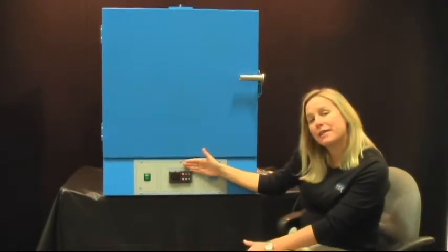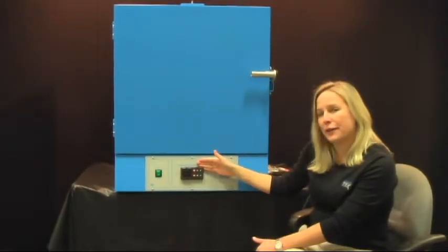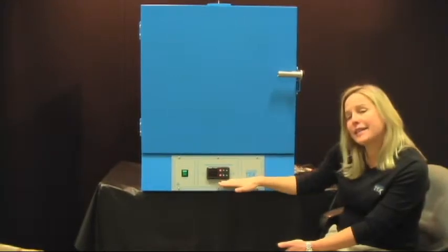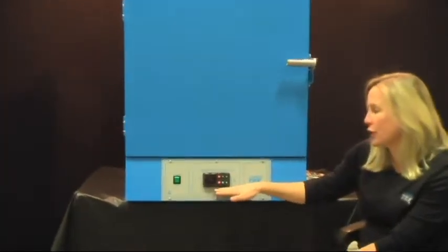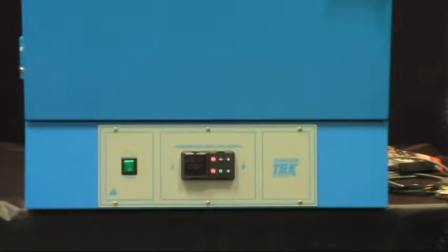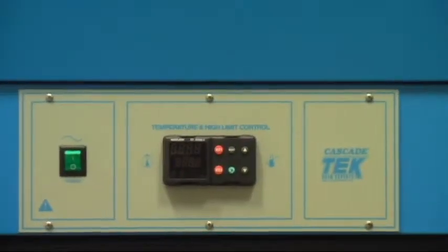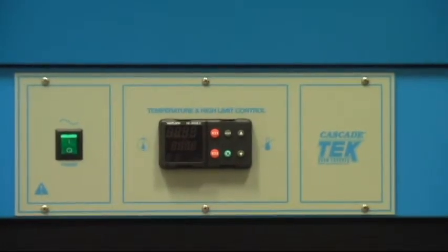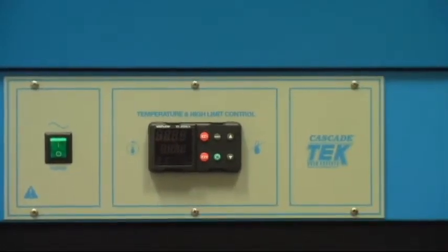Let's say a few words about the Cascade TEK control panel. The Cascade TEK oven controller is a fully programmable ramp and soak controller. What that means is that you can write what we call temperature profiles.